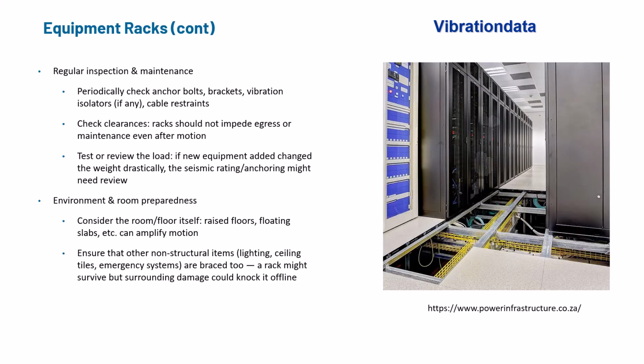Here's more about equipment racks. There are good reasons why in buildings these are mounted on raised floors. Cable runs can go underneath the floor so no one trips over them, and there are good thermal reasons for having that raised floor and air volume underneath. But there's a trade-off: that arrangement can cause dynamic amplification through the floor supports and into the racks or servers. Be aware of that trade-off.